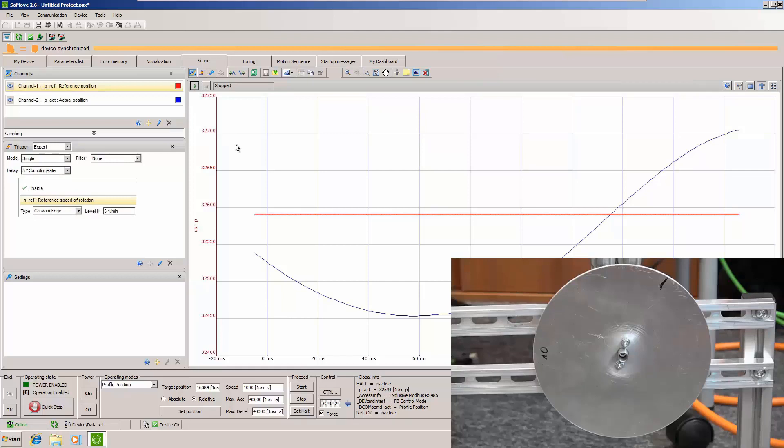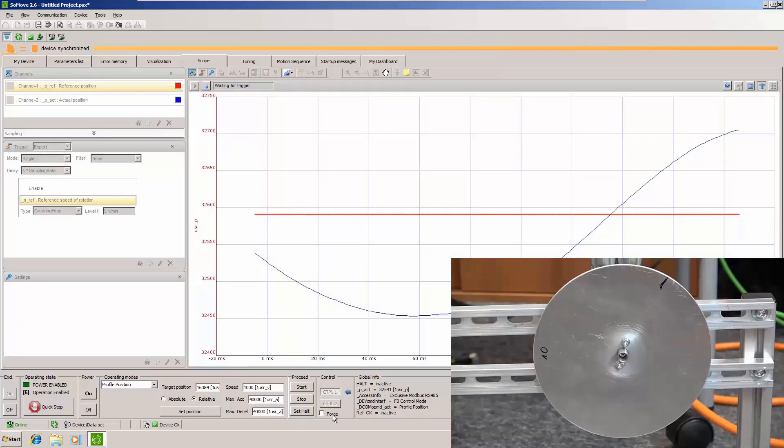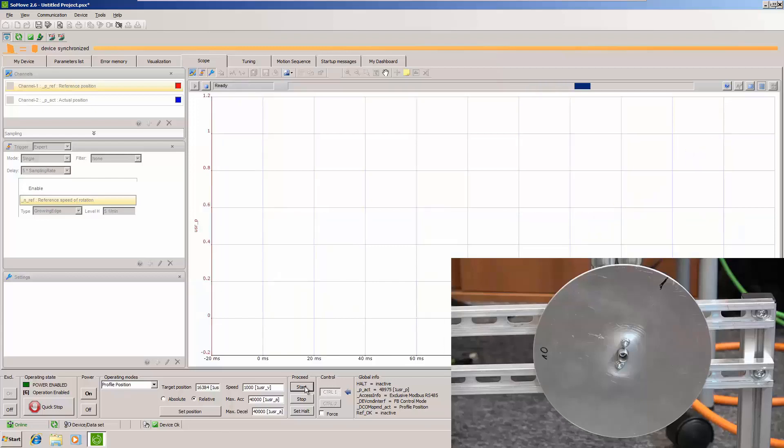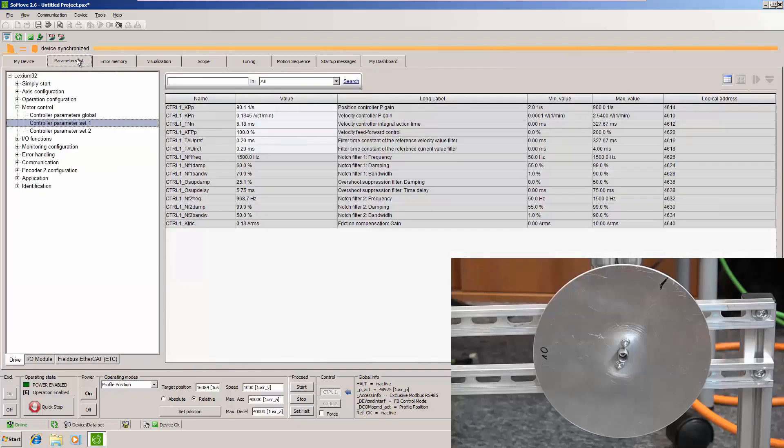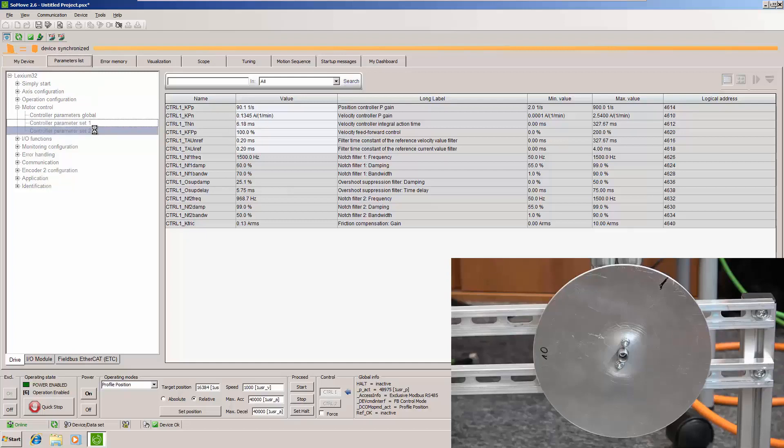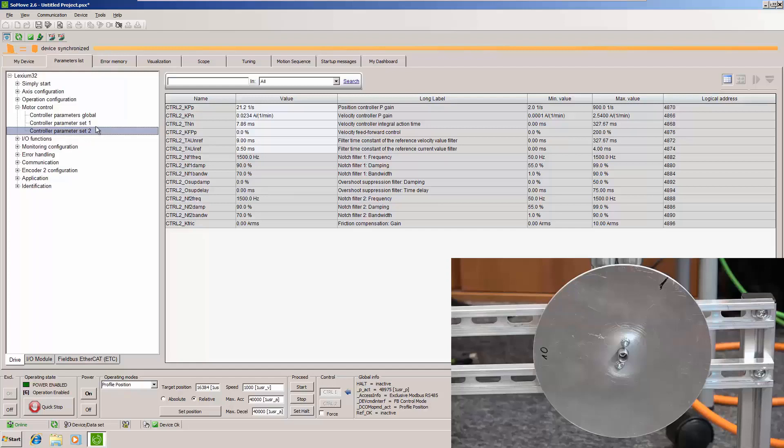And let's check the results of tuning. So we will start the rotation. It's almost invisible to see the one circle of this motor. But here you can see that the reference and actual position are more or less the same. And here you can see that control set is different after tuning. It's much sharper.